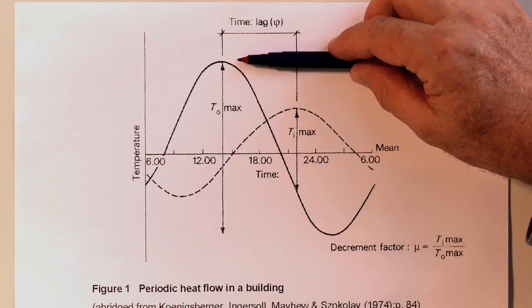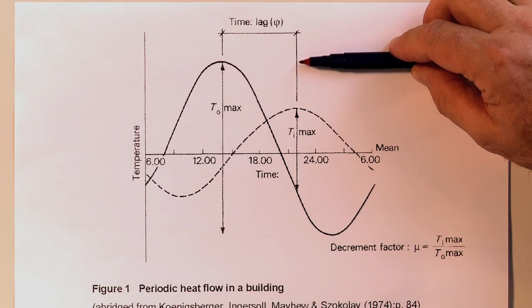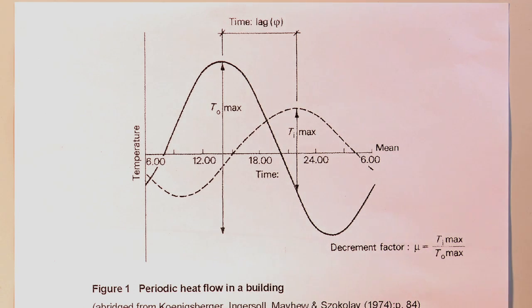Every wall configuration has a different decrement factor. It's never one, because if the decrement factor were one, then the outside air temperature would eventually be achieved internally — and we don't want that. We don't allow it to occur in our building design, and so that's why we use brick, gyprock, some form of insulation, and the air gap between the outside and inside skin of the wall.